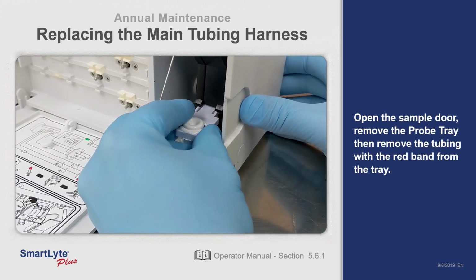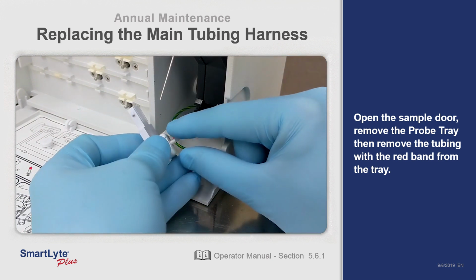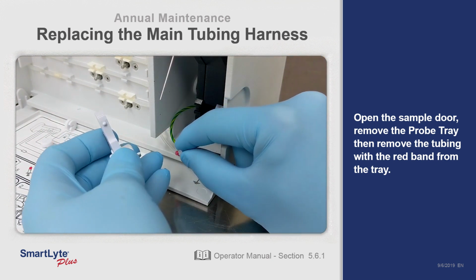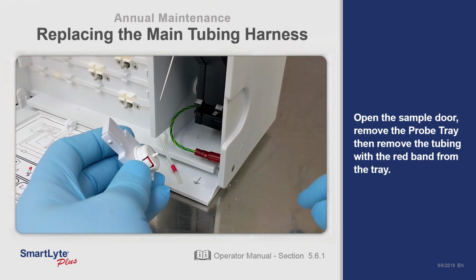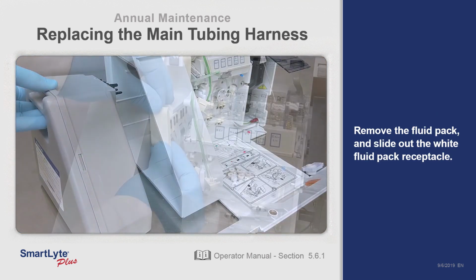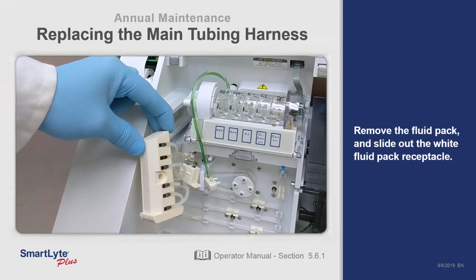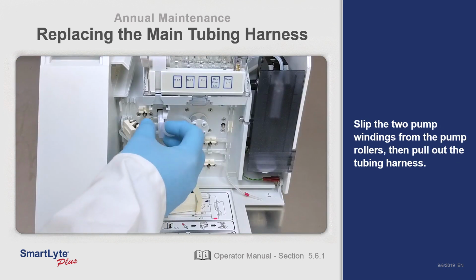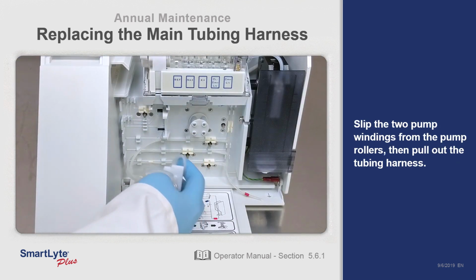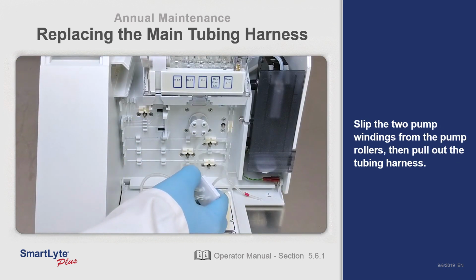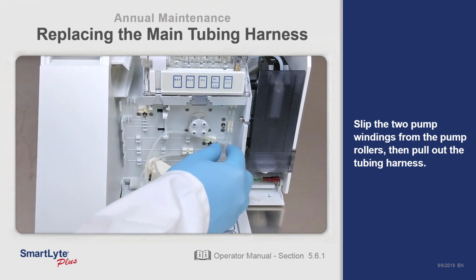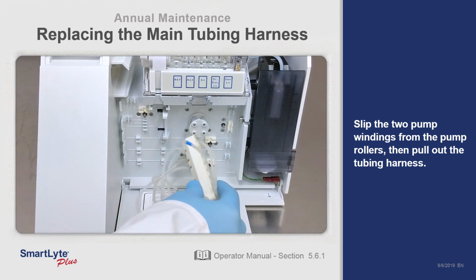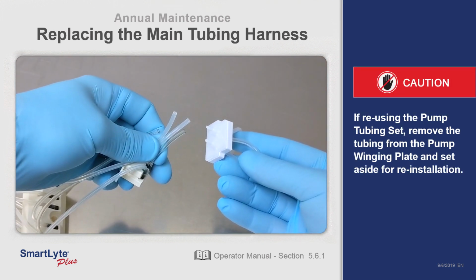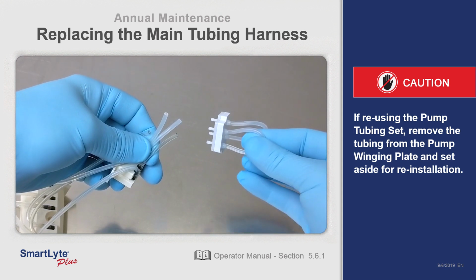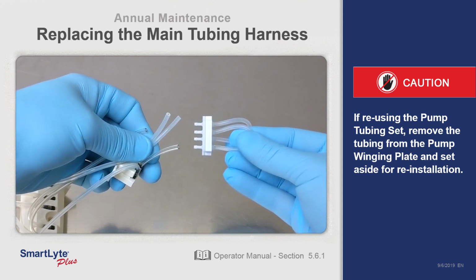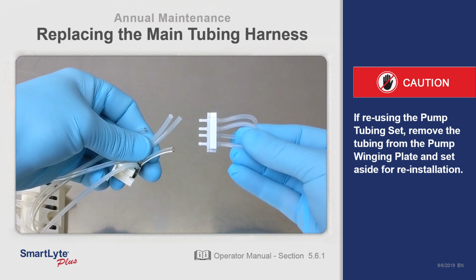Open the sample door, remove the probe tray, then remove the tubing with the red band from the tray. Remove the fluid pack and slide out the white fluid pack receptacle. Slip the 2 pump windings from the pump rollers, then pull out the tubing harness. If reusing the pump tubing set, remove the pump tubing from the pump winding plate and set aside for reinstallation.